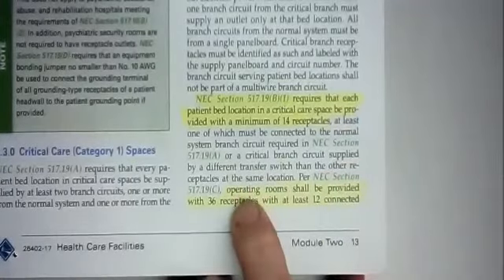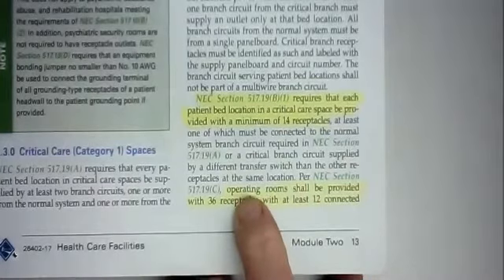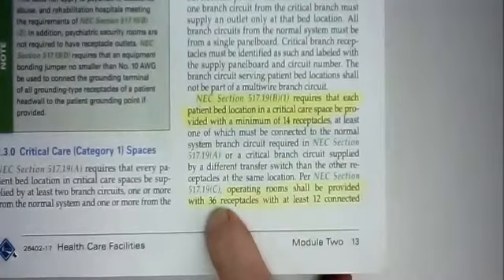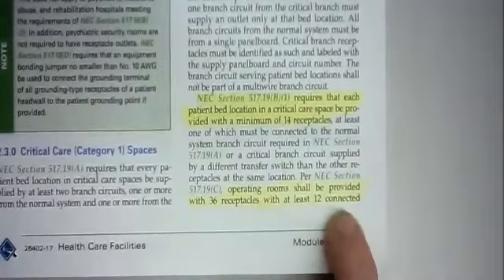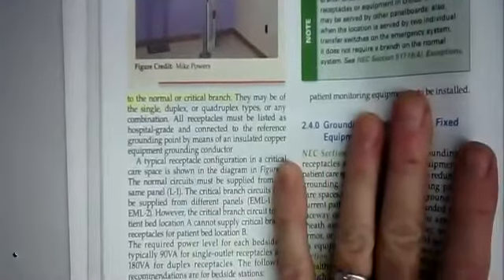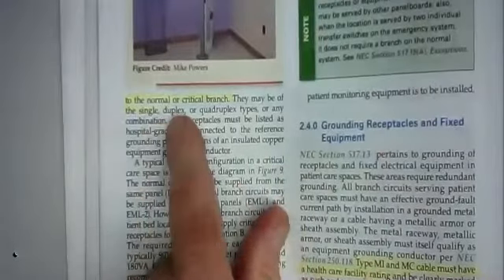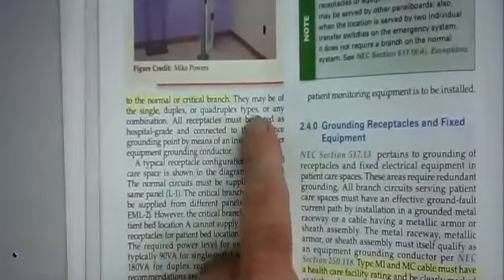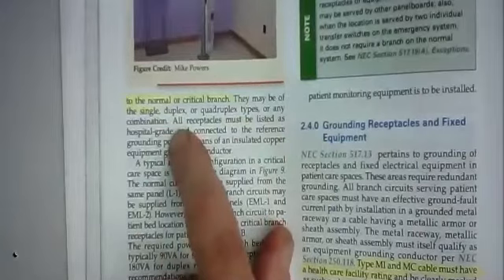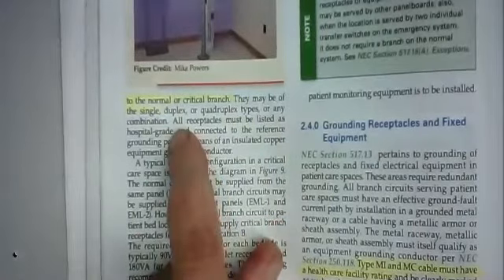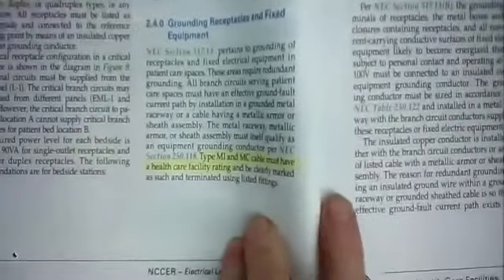In an operating room, per NEC section 517.19(C), operating rooms shall be provided with 36 receptacles, at least 12 of them connected to normal power, at least 12 of them connected to emergency power, to the normal or critical branch. They must be of single, duplex, or quadruplex types or any combination. But 36 receptacles, 12 and 12, 12 on normal power, 12 on critical power.